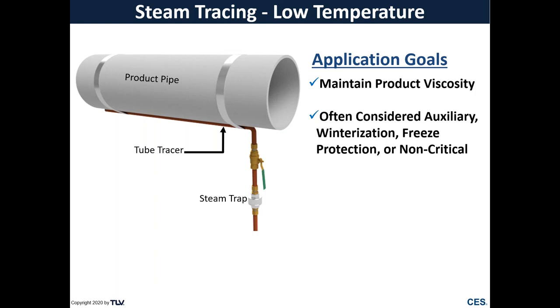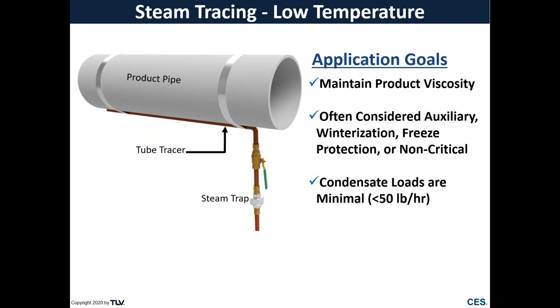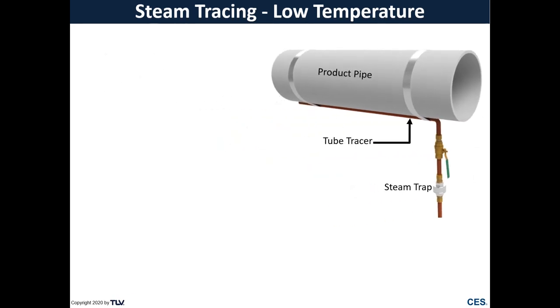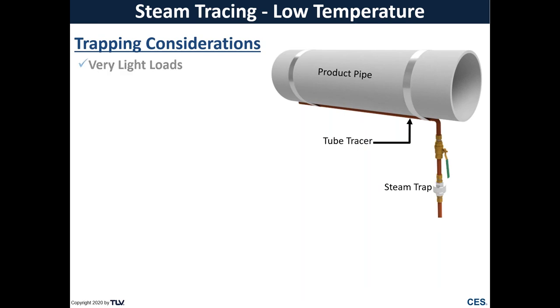So these are often used for winterization or freeze protection, just to keep product pipe warm. And our condensate loads are typically fairly minimal, usually well less than 50 pounds an hour, probably down into the 10 to 20 pound an hour range. So our trapping considerations for a low temperature steam tracer. One is it's going to be very light load, so we don't need a very large steam trap.